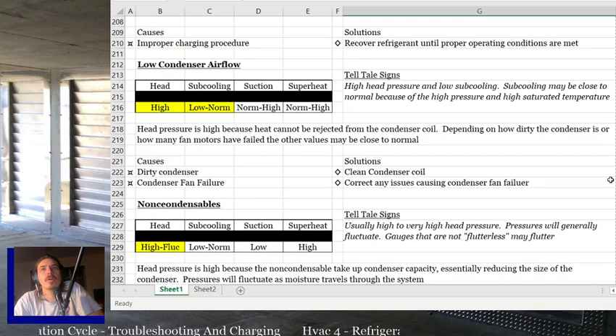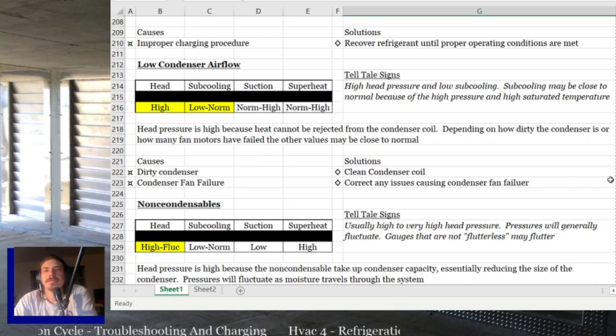Low condenser airflow will be high head pressure, low to normal subcooling. The low condenser airflow, so like you got a dirty condenser or something like that. A lot of times subcooling's pretty close. The main reason is you got a dirty condenser. It's basically operating inefficiently. But if you got a dirty condenser, and your head pressure should be at 100 degrees sat temp, but it's at 130 degrees sat temp, and it's 80 degrees outside, you got a 50-degree temp difference. You're still going to give off heat.